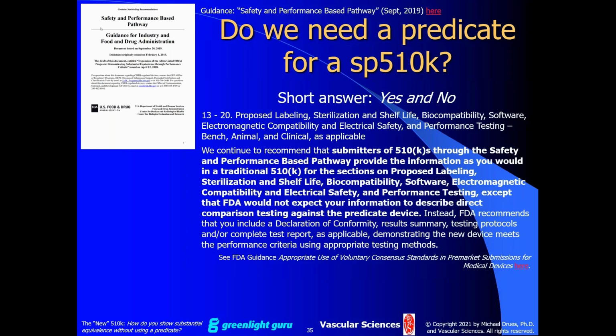Most of them have to have some kind of a shelf life. Most of them, if it's coming in contact with a patient, need to have some demonstration of biocompatibility. I'm not saying that those things are not important. Of course they are important. But in my book, those things have nothing to do with substantial equivalence. Substantial equivalence is a direct comparison to either a predicate, if it's a traditional, or to your pre-change device, if it's a special, or if it's an abbreviated or an SP 510K, the comparison to the standard. That's what you should focus on when it comes to substantial equivalence, not these other things. That just gets in the way.